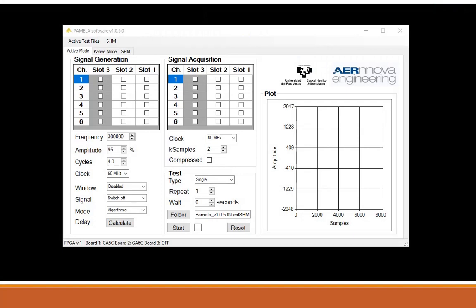Well, the active mode can be helpful to run individual tests on a given specimen. Both the signal generation and the acquisition can be configured. Regarding the generation, along with the selection of the driven sensors, parameters like frequency, amplitude, up to 48 volts peak-to-peak, or number of cycles can be selected. The generated sine waves can be modified by applying different windows such as Hanning, Hamming, etc.